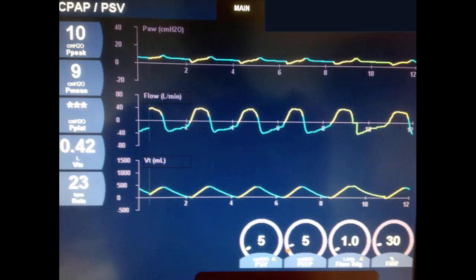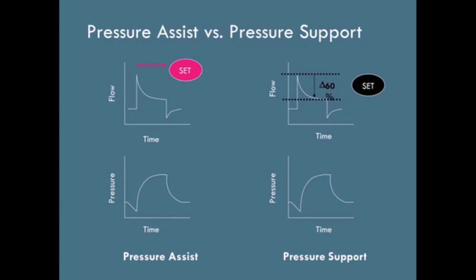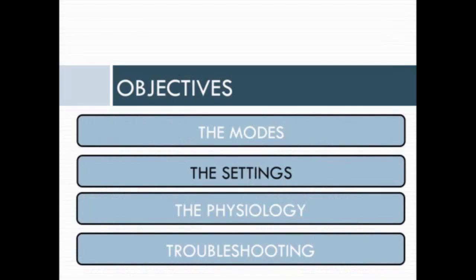Let's review the difference between pressure assist control and pressure support. On the left with pressure assist, you set an inspiratory pressure and that pressure is delivered for as long as the inspiratory time is set. Pressure support is different — what terminates the breath is a drop in flow. If the patient doesn't pull as hard against the ventilator, the flow drops quicker and the breath is shorter. Although you set the percent drop in flow that will stop the breath, the patient's interaction with the ventilator determines when that breath stops.